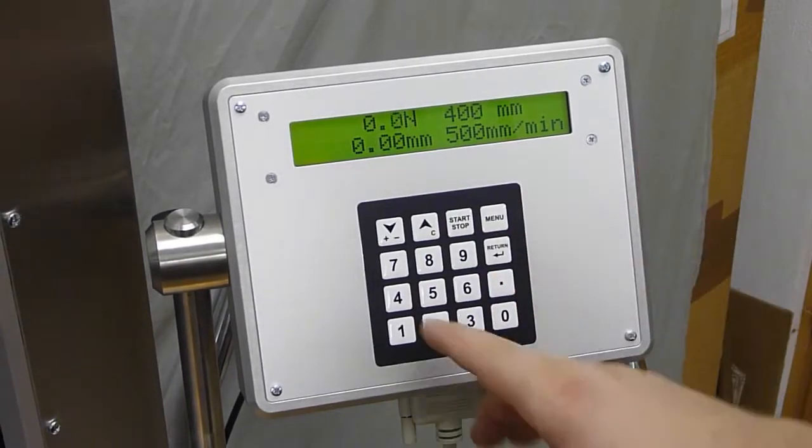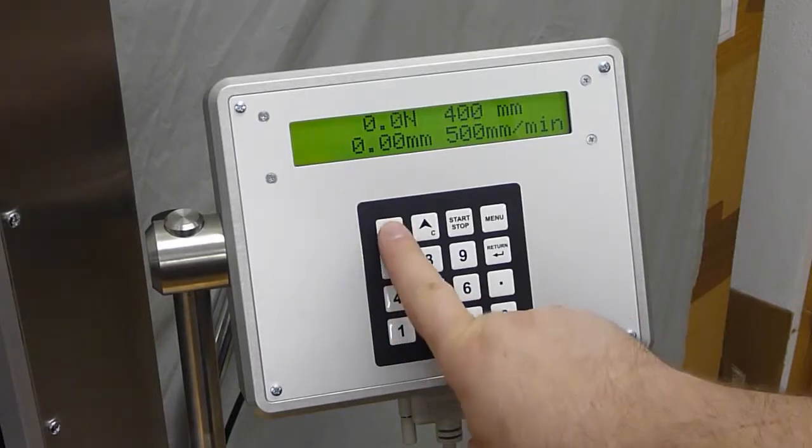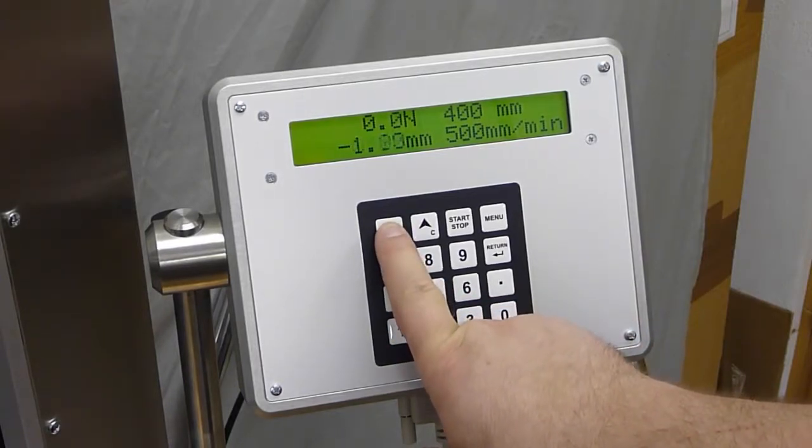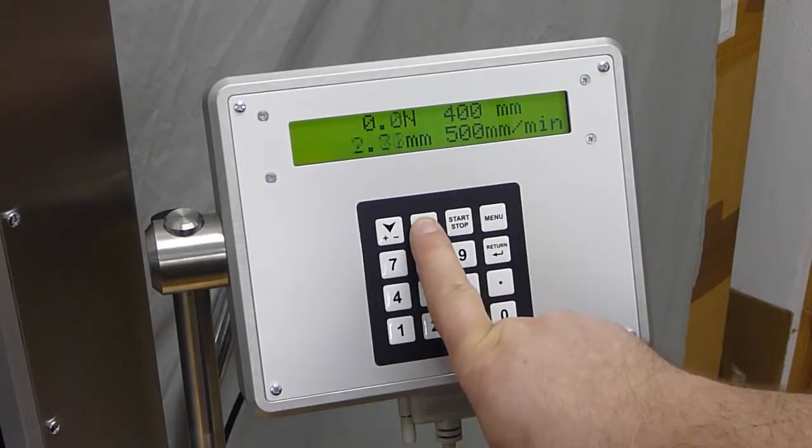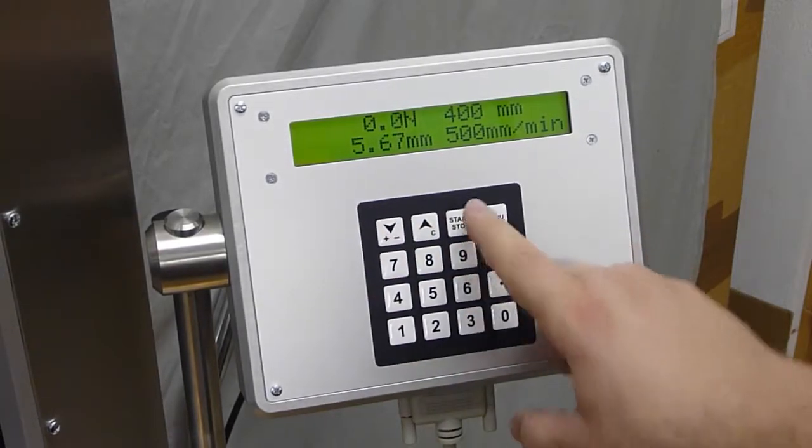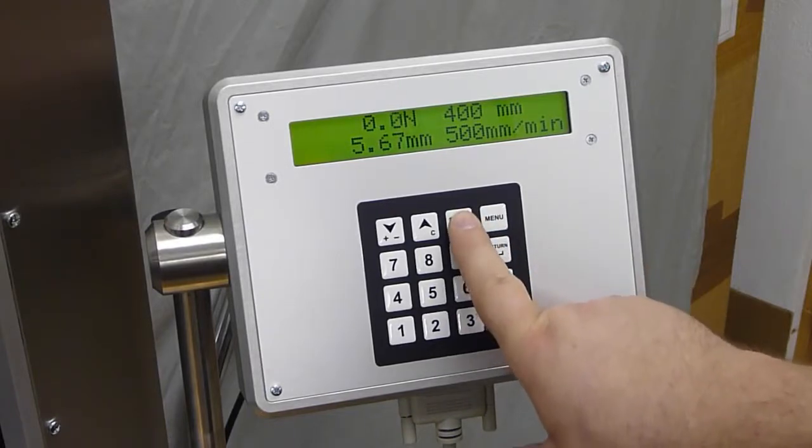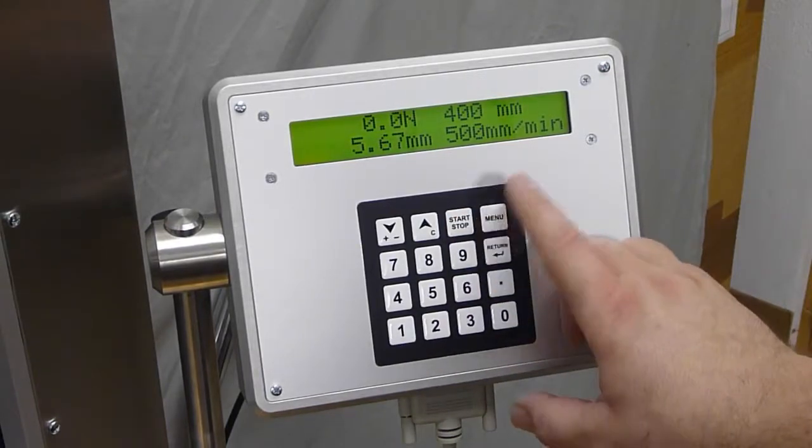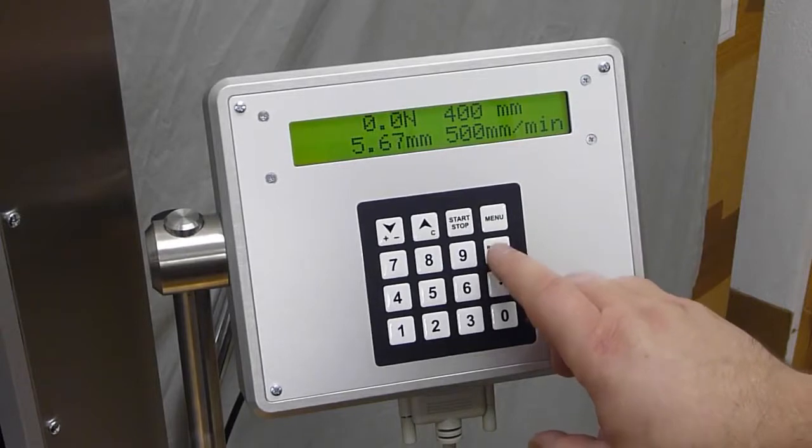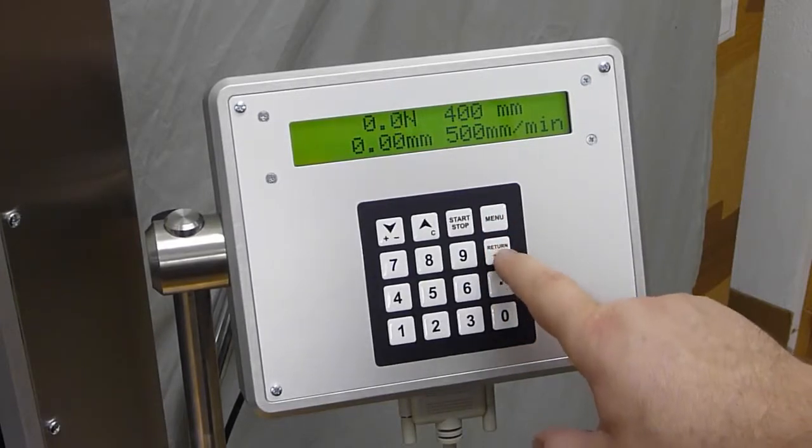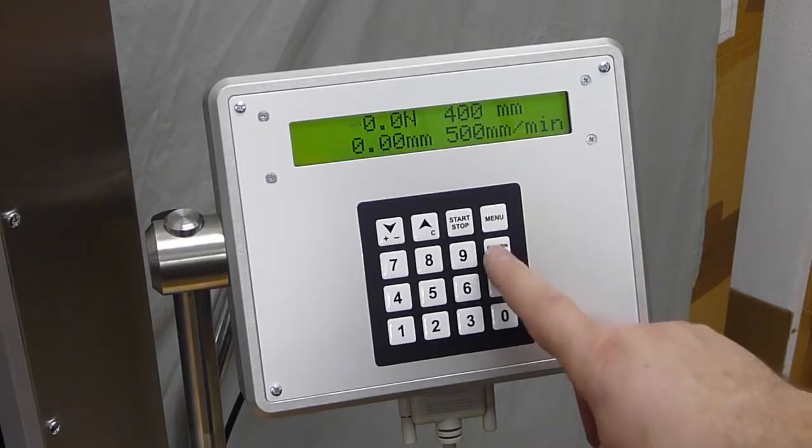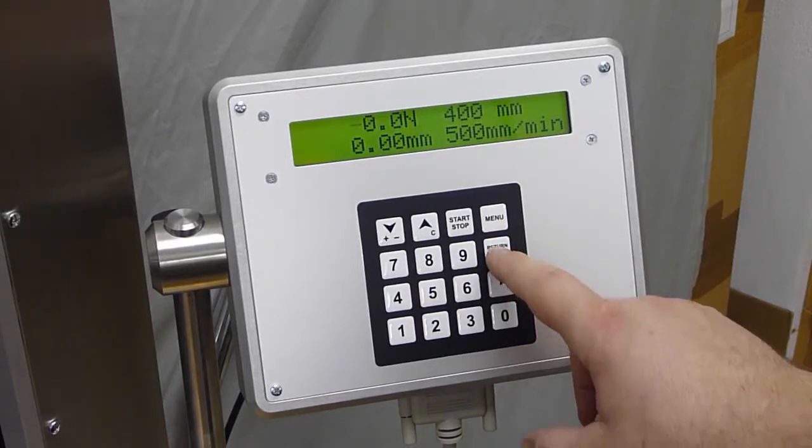The shortcut keys: down key to manually move down the machine, up key to manually move up the machine, start-stop to start and stop test, menu for user menu, return always sends the machine to zero position. In the test, the return key has two functions: break test and send the machine automatically to start position.